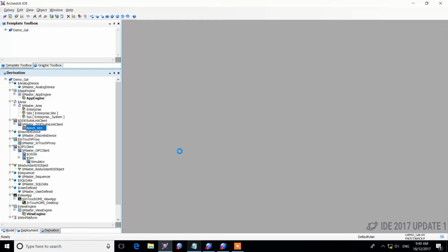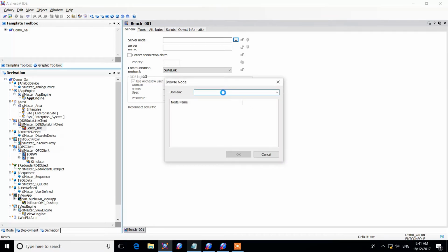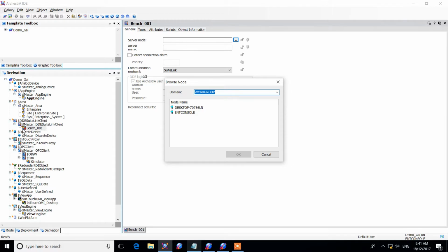Obviously this video assumes you're not overly familiar with ArchestrA and with System Platform. It's very much an introductory kind of view to things. Obviously if you're familiar with this software, you're going to understand what things like the ticks and the crosses mean. As a quick overview, squares mean an undeployed object. A square with a diagonal stripe through it, black and yellow, indicates an object that has been deployed but has been changed since, so the deployed version is not the current version. The little red tick indicates that the object is currently checked out and being edited.